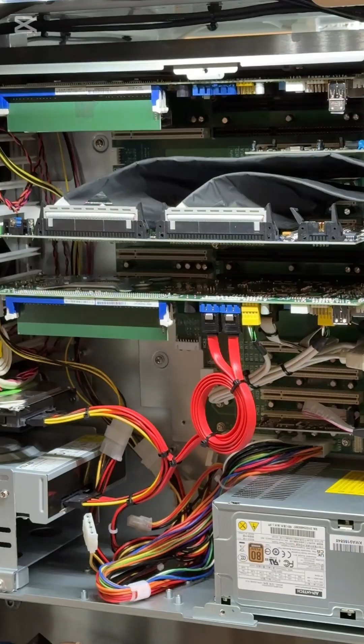So this board essentially takes in feedback from the encoders. It receives information from the encoders, everything that rotates, what angle to turn to and how far it has gone. It gathers that information, as well as parameters coming from the amplifiers, which power the motors. And then the DMC sends signals out to run the motors at a certain speed, position, and torque. It sends information on what speed, to what position, and with what torque to move the motor back and forth.